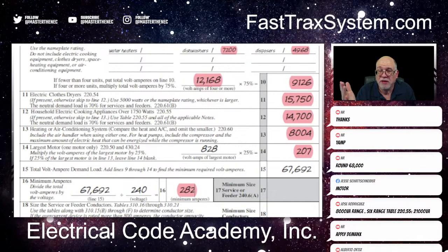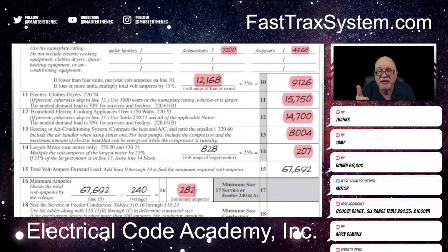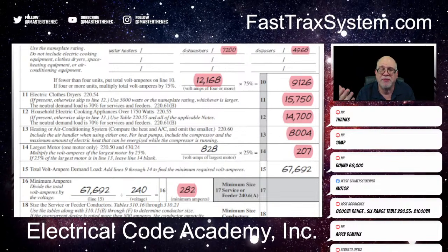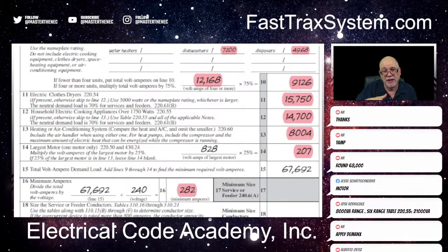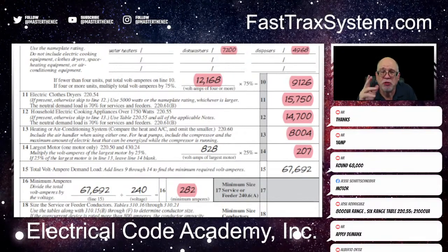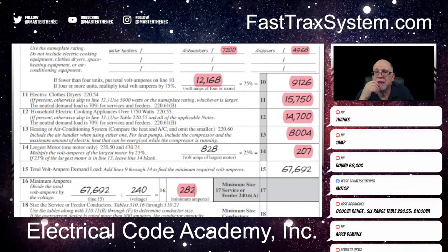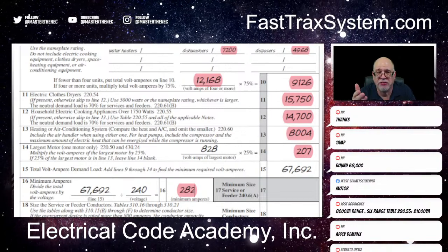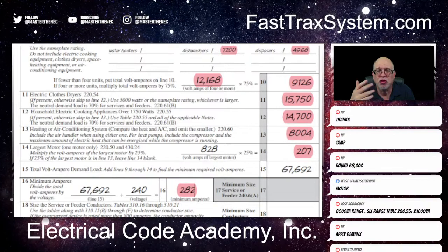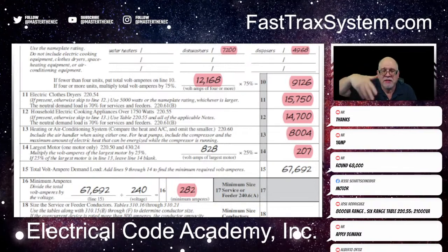Make sense? I don't want you to dwell on it and say, oh Jesus, I must have done something wrong. If it's only 1 amp off, then choose the best possible answer, okay? That's the best way to tackle it. But when I round, I don't round neutrals. And so this is a neutral calculation. So that's another reason that I don't round the neutral when it comes to VA values.